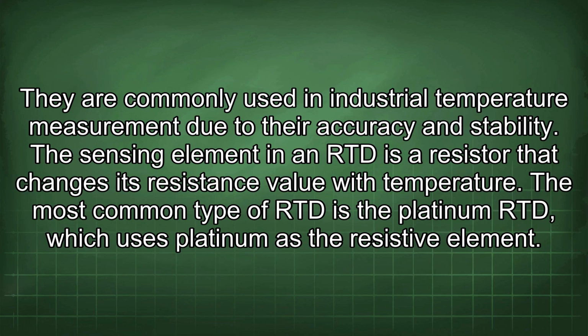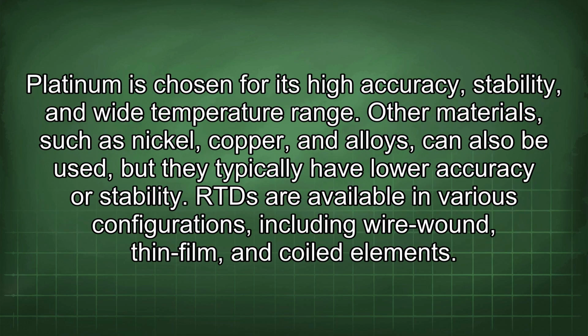They are commonly used in industrial temperature measurement due to their accuracy and stability. The sensing element in an RTD is a resistor that changes its resistance value with temperature. The most common type of RTD is the platinum RTD, which uses platinum as the resistive element. Platinum is chosen for its high accuracy, stability, and wide temperature range. Other materials, such as nickel, copper, and alloys, can also be used, but they typically have lower accuracy or stability.